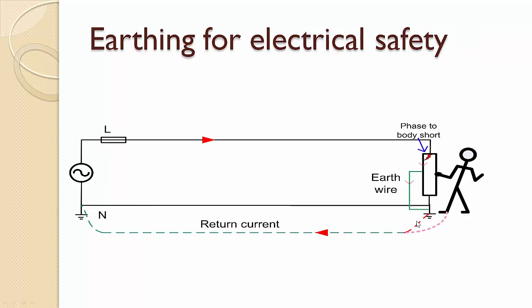Here one question may arise. We have noticed that in this case the supply is earthed at this point, and earth current through the fault flows through the supply earth to complete the loop. We can also appreciate that had the supply not been earthed, there would not have been a complete path for the fault current to flow through the earth.